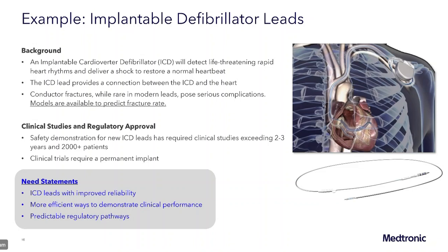So you can imagine now the importance of these wires. If they break, there are many failure modes that can happen, and they're all serious. It can range from inappropriately detecting rhythms. If the wire is broken and making make-break connections, noise, then the device might think that you're having ventricular fibrillation and you're not, and deliver a shock.